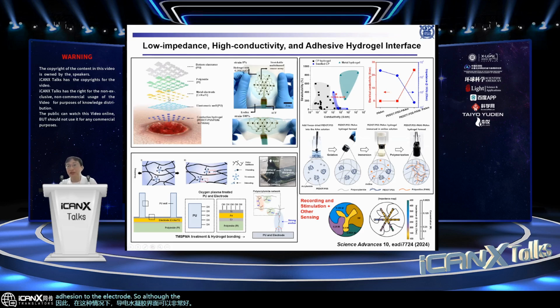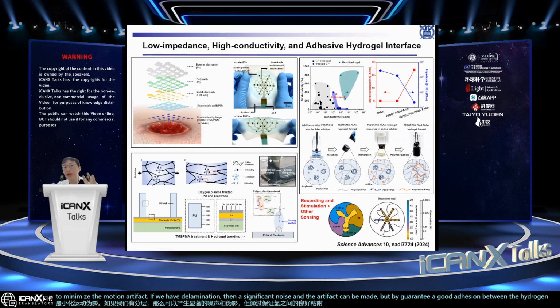So although the skin deforms, since we have good adhesion between the hydrogel and the metal electrode, as well as the hydrogel and the target tissue, the skin tissue, a reliable signal can be achieved. And that is also very important to minimize the motion artifact. If we have delamination, then significant noise and artifacts can be made. But by guaranteeing good adhesion between the hydrogel and metal electrode, as well as the hydrogel and the skin, much more reliable sensing could be achieved.